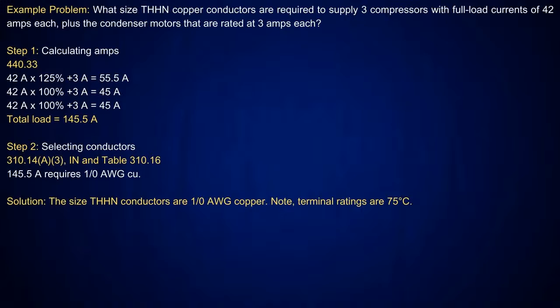Go to Table 310.16, 75 degree C column. The next size above that is 150 amps, which requires a 1-aught conductor. Now, the thing I like to point out here: have I changed any of these calculations, really? The format, the layout, everything is exactly the same. The only thing you've got to remember is how to do each one of them. But you just have to be careful, because you don't want to make the assumption you can just wire everything with a 1-aught.